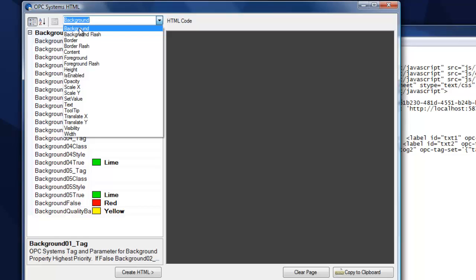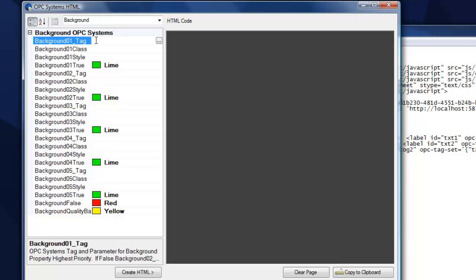Here under the background color, we can see we can assign up to five different boolean points, each one of them having the highest priority at the top. And if it's true, the first one's true, then we'll set it to the first color. If it's false, it'll move down to the second tag that's defined, if it is, and change it to the second color that's defined there.